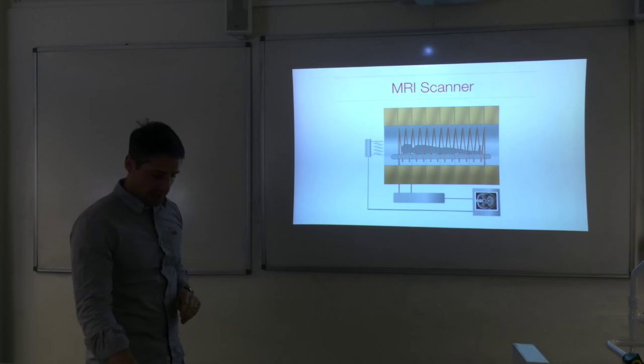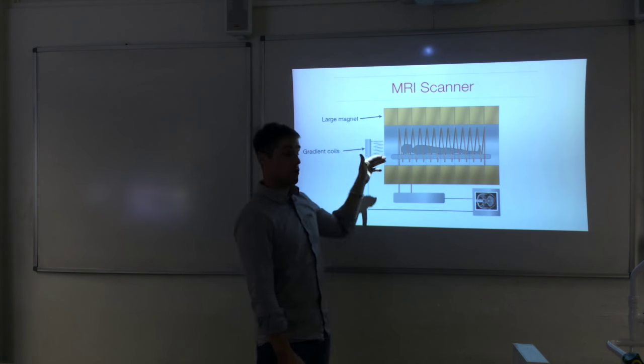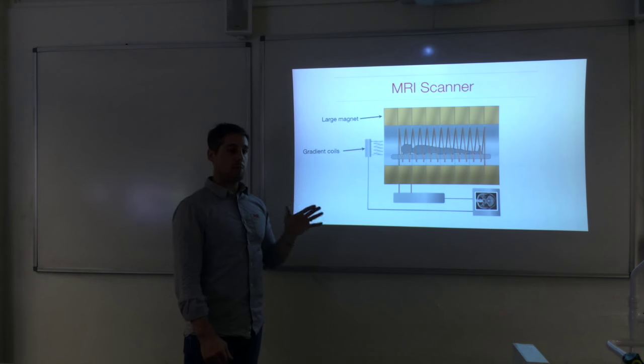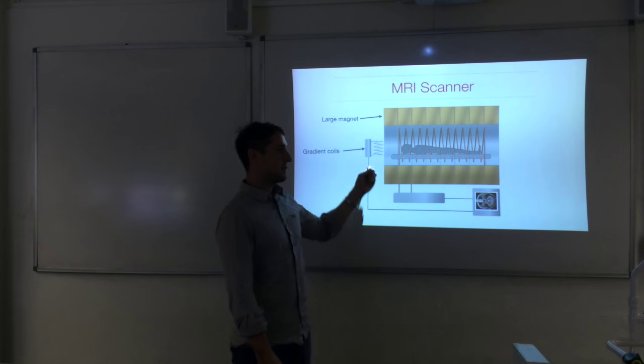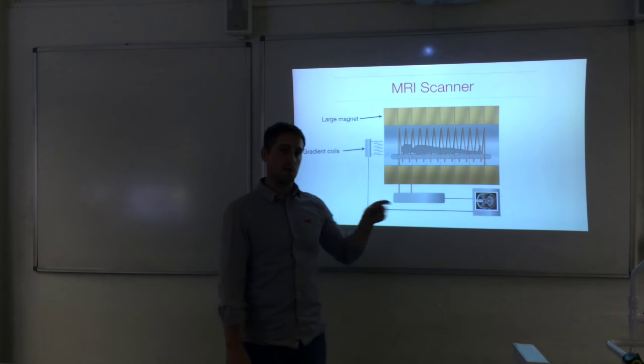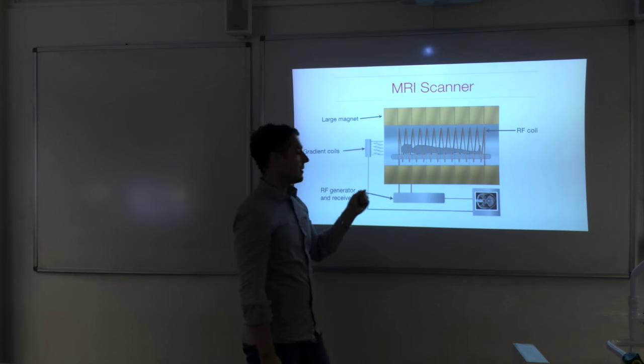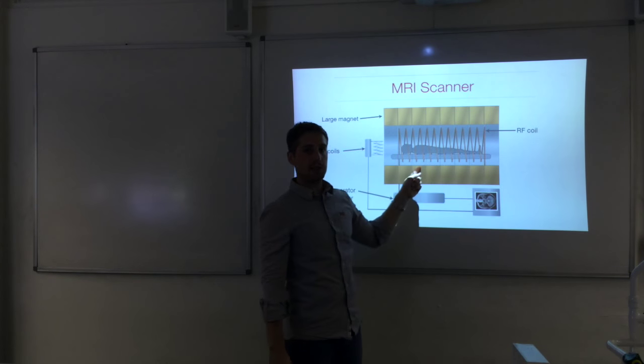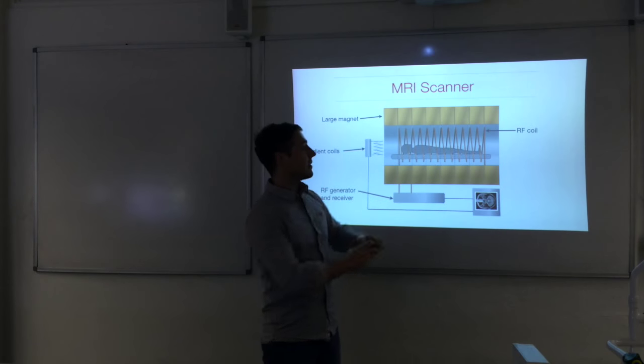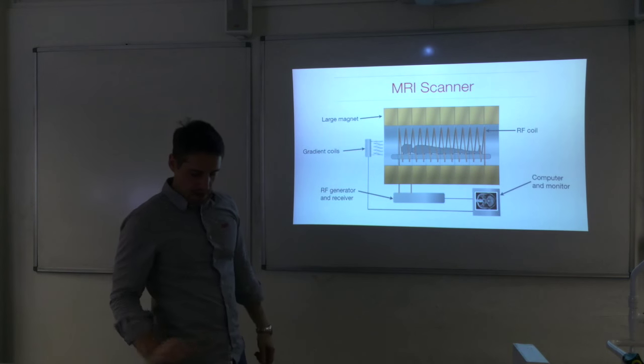An MRI scanner has several components: a large magnet providing the strong uniform magnetic field that the patient is inside; gradient coils that adjust the magnetic field strength throughout the body, varying the Larmor frequency spatially; and a radio frequency coil with generator and receiver that transmits radio photons into the body and receives the signals emitted when nuclei relax. A computer controls everything and the monitor displays the image for the radiologist.